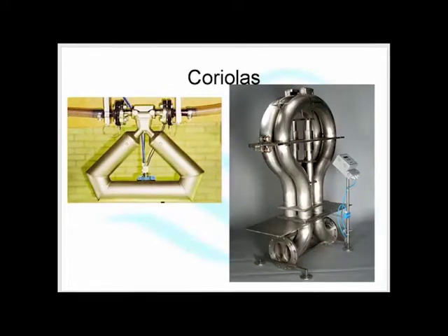So the industries that use Coriolis are the sort of industries that can afford to use Coriolis: pharmaceuticals and oil and gas. Now, looking at these big Coriolis meters here, bear in mind the way it works is by flapping that big pipe backwards and forwards repeatedly and measuring how much that big pipe twists. Can anybody see the Achilles heel of the Coriolis meter?